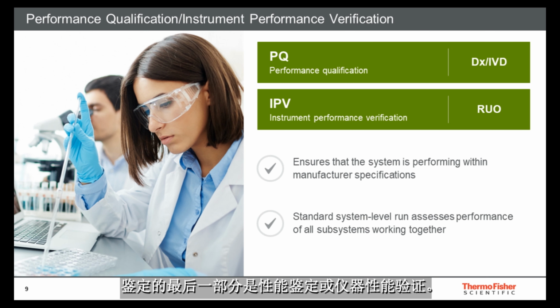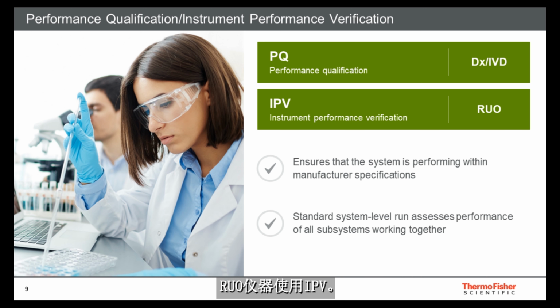The final component of a qualification is performance qualification, or instrument performance verification. Remember, Thermo Fisher Scientific uses PQ for its DX or IVD instruments and IPV for its RUO instruments. By definition, the performance qualification, or instrument performance verification, will establish with confidence that the process equipment or ancillary systems are performing to manufacturer recommendations by demonstration with objective evidence.